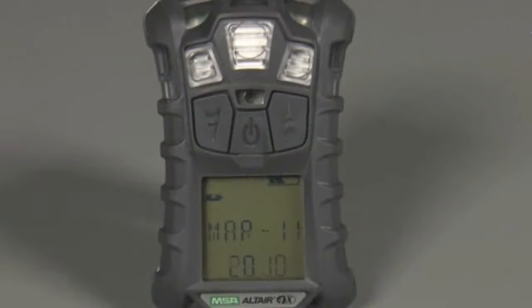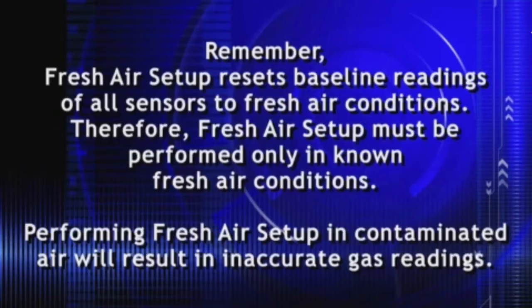In addition to the fresh air setup prompt that occurs during startup sequence, users may elect to perform fresh air setup at any point when the instrument is in measure mode. Remember, a fresh air setup resets baseline readings of all sensors to fresh air conditions. Therefore, fresh air setup must be performed only in known fresh air conditions. Performing fresh air setup in contaminated air will result in inaccurate gas readings.